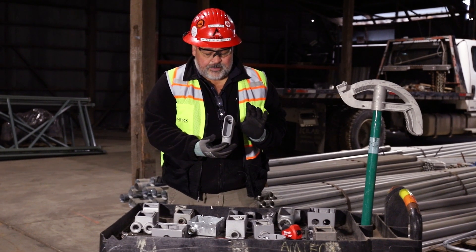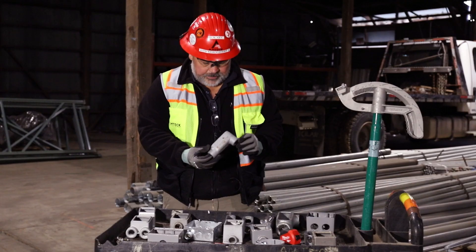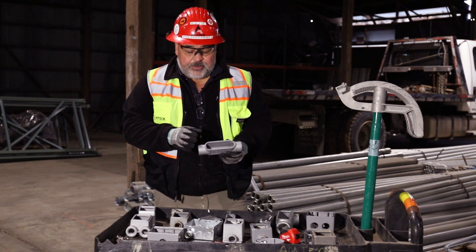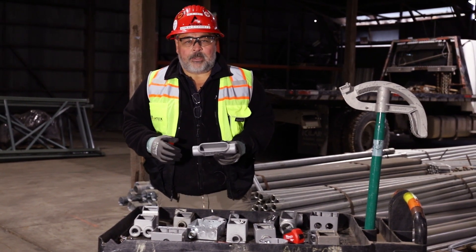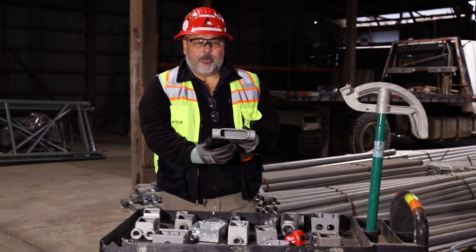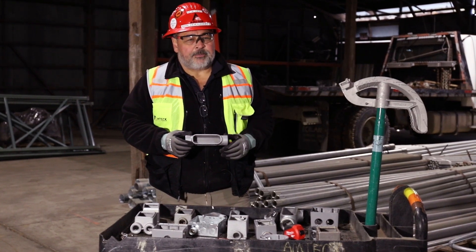Then we have these fittings which we call condulets. This is an LB, commonly used to make a quick turn on threaded conduit. Then we have a C conduit — this goes straight through. What this does is allow us to go through, and we're only allowed 360 degrees between one enclosure and the next. Sometimes with rigid conduit in confined areas we'll have a lot of bends in a short distance, so we put this in the way to give us a pull point — from this point to the right we've got 360 degrees or less, and from this point on we've got another 360 degrees possible.